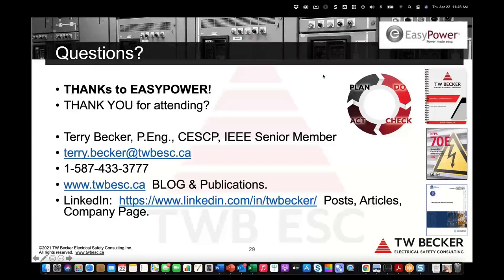An incident energy that the worker then uses following that energized electrical job workflow that I mentioned today, to determine what PPE they need. They procure, check, and inspect it, don it, do the at-risk work, whether it's DC or AC. At that point, it doesn't matter. All right. Here's one from Anthony. Is taking a voltage measurement in an energized 480-volt motor control center considered hot work? And then corollary, is troubleshooting on 480-volt equipment considered hot work?